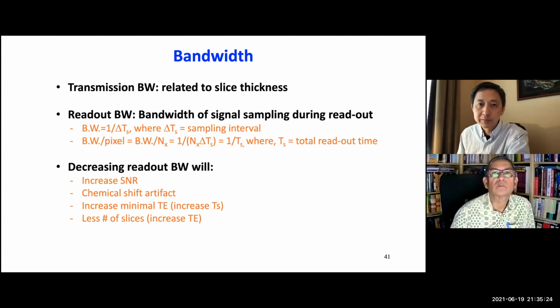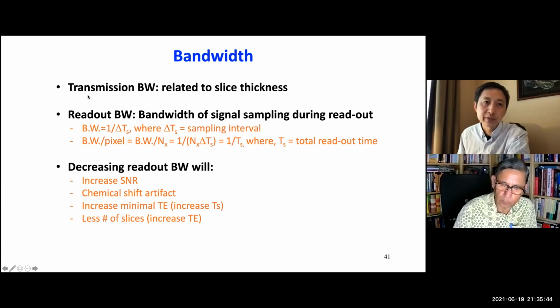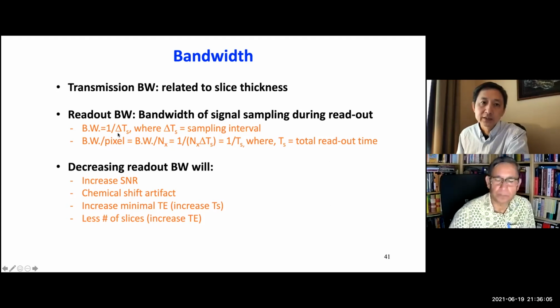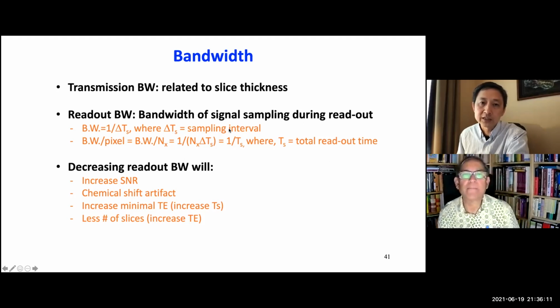So among all of those parameters, bandwidth is probably the least familiar parameter for most people, so I want to highlight a little bit about what bandwidth is. It is indeed a parameter that can be adjusted, but many technologists are afraid of bandwidth because they don't understand it. There are two kinds of bandwidth. First is transmission bandwidth, another is readout bandwidth. The transmission bandwidth is not adjustable on the operator user interface. So when we look at the MRI console, the bandwidth means the readout bandwidth. The readout bandwidth is 1 over delta TS, where delta TS is a sampling interval in the readout time. During the readout, delta TS is a sampling interval.